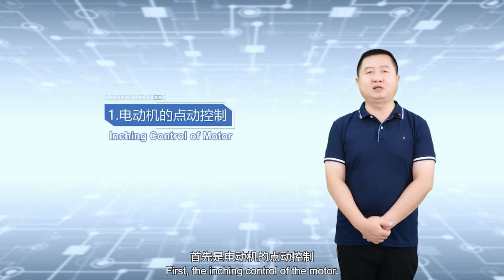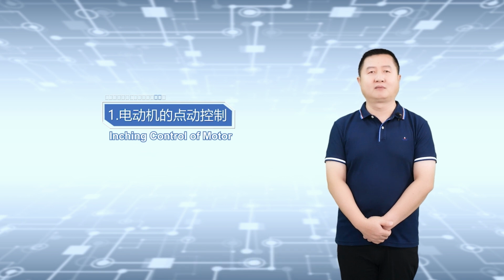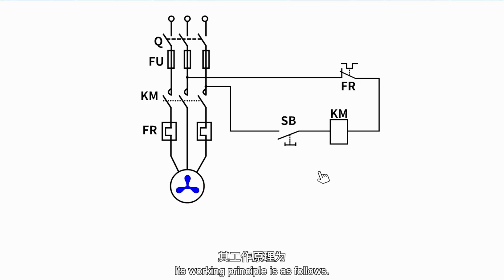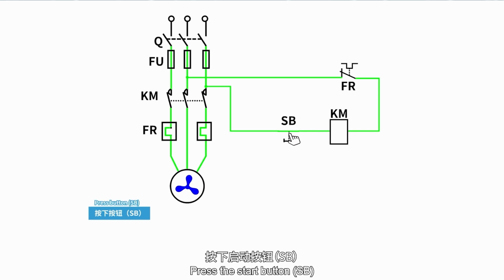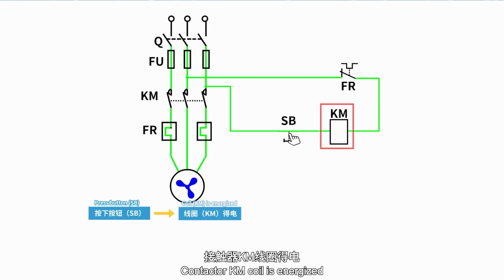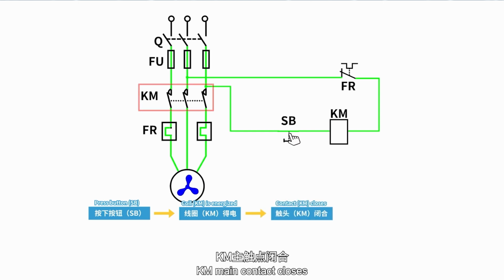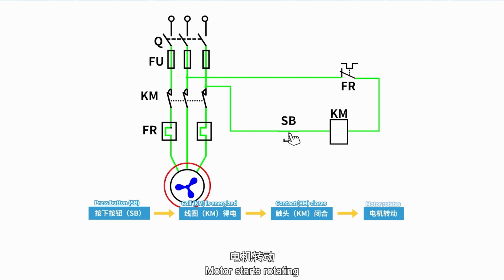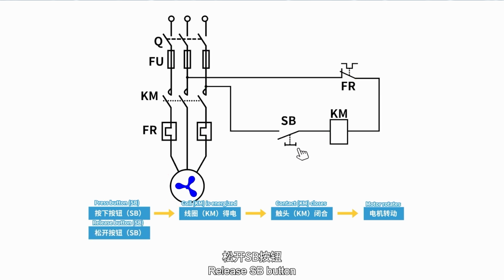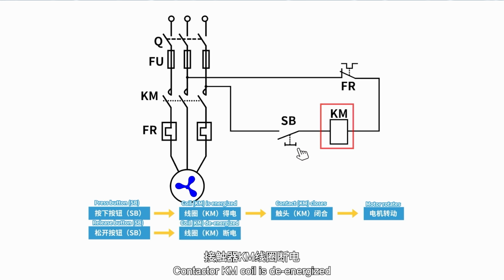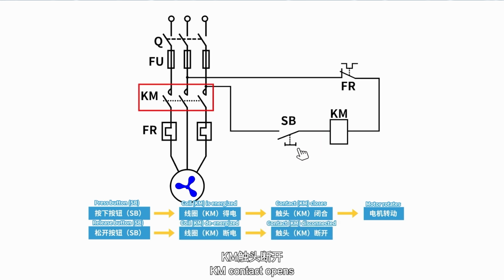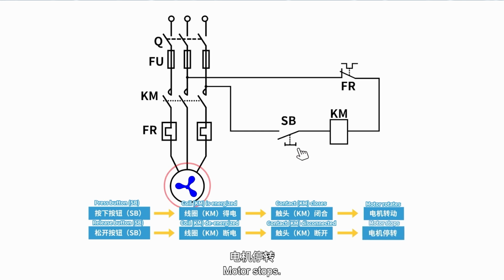First, the inching control of the motor. Its working principle is as follows. Press the start button SB. Contactor KM coil is energized. KM main contact closes. Motor starts rotating. Release SB button. Contactor KM coil is de-energized. KM contact opens. Motor stops.